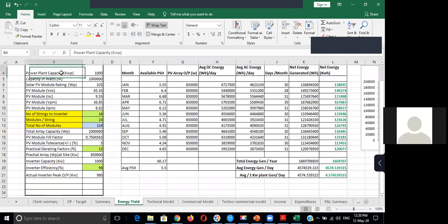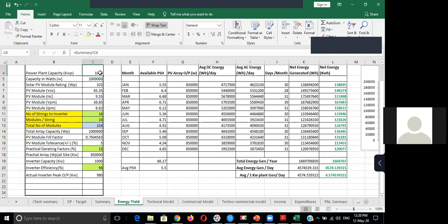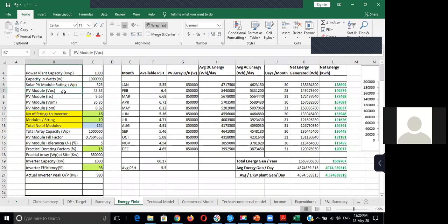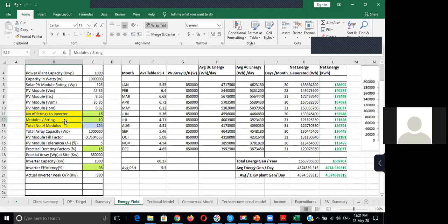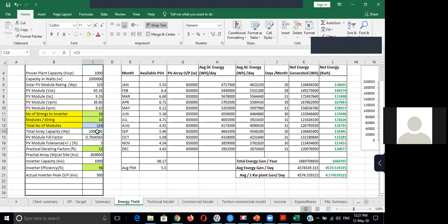This is a plant capacity in terms of kilowatt, and this is the capacity in watts. I have calculated a one megawatt analysis here. And this is a solar PV rating of an individual module - 325 watts. And its open circuit voltage, short circuit current, voltage at maximum power, current at maximum power. So in terms of electrical, these five parameters are very important. And in terms of string designs, how many numbers of strings per inverter and how many strings are there, and what is the total number of modules and what is the total array capacity I'm going to achieve out of this design.